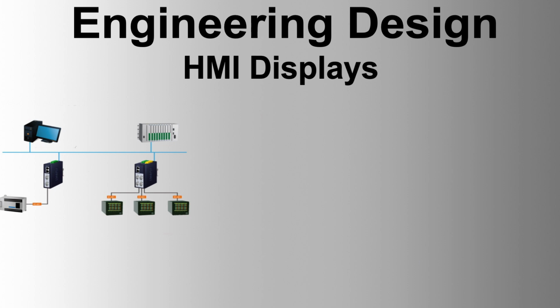Graphics should be logically built from major process equipment, e.g. vessels, columns, pumps, compressors, and control schemes. They should be oriented from left to right, with pipes or signal lines entering from the left and leaving on the right. Crossing pipes or signal lines and unnecessary details should be avoided. Process equipment that cannot be controlled, e.g. isolation and bypass valves, should not be shown unless necessary for task understanding. Displays should be task-driven, showing major equipment control aspects and avoiding use of the outer edges of the screen, which may be obscured.